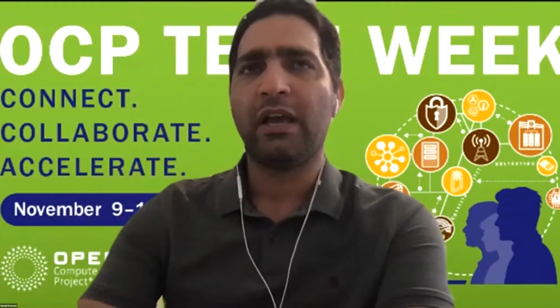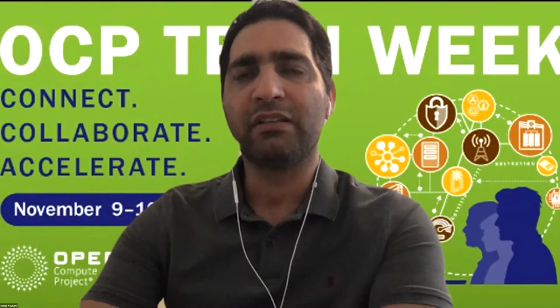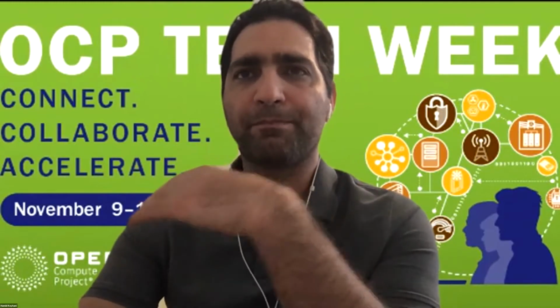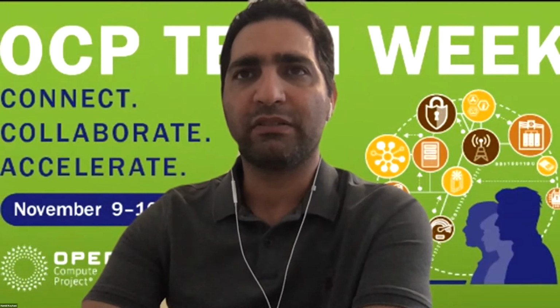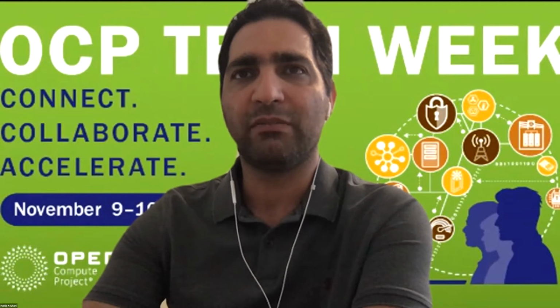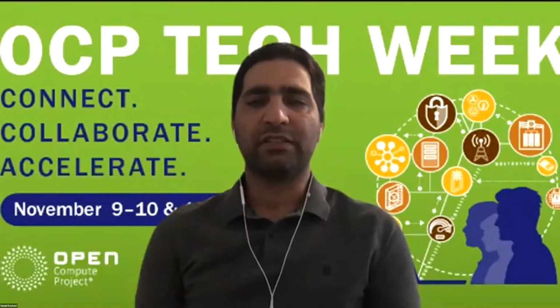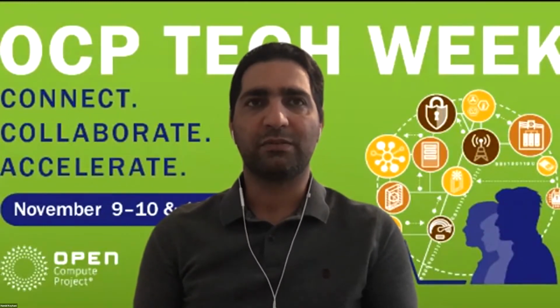So on V2, is 1 kV stronger than 2 kV? I thought that at 1 kV is where your varistors start to break, versus 2 kV. So maybe it's 1 kV differential mode and 4 kV common mode. Now the legal requirement is 1 kilovolt and 2 kilovolt. So V2 was double the legal requirement, and I think now it's back to the legal requirement. So actually V3 is more stringent in that case, I would say, yes?